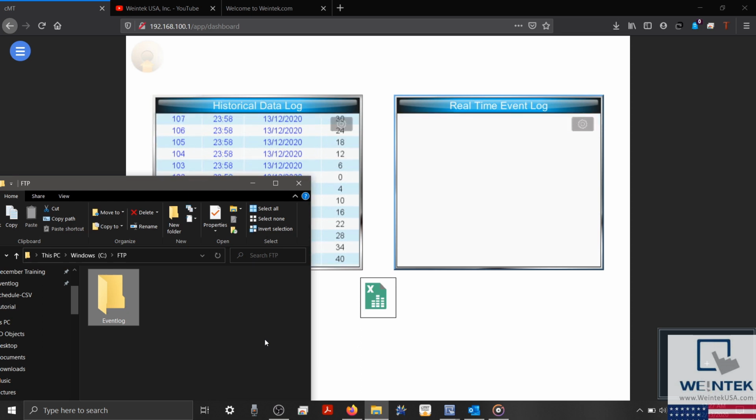Alright, so I've downloaded the project to my HMI, and using WebView, I can view my HMI's display. I've configured our HMI's time to 1 minute before the preset time of our scheduler, and so our export will trigger automatically in a few seconds. I also have the FTP folder open on my desktop. With our backup triggered, we'll wait the 10-second delay that I've configured prior to transfer.